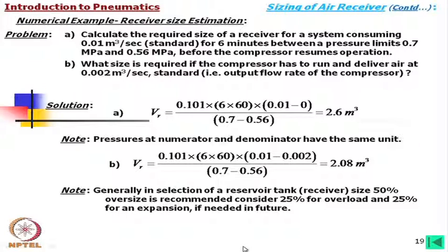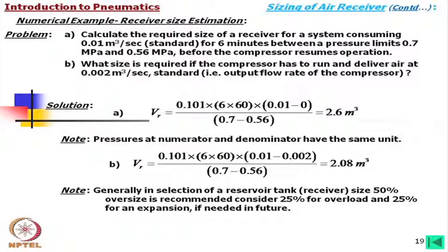Say you are designing such a compressor and reservoir for an industry, then first of all you have to consider at least 25% overload may be there. So 75% directly coming over there, and usually what happens after setting up, you may need to add one or two more equipment with that. So another 25%, that means whatever capacity is wanted for an industry, usually if it is in the beginning stage, and considering that is the 50% requirement, we usually consider 100%, and then we design the compressor.